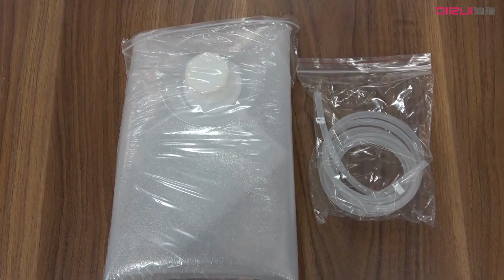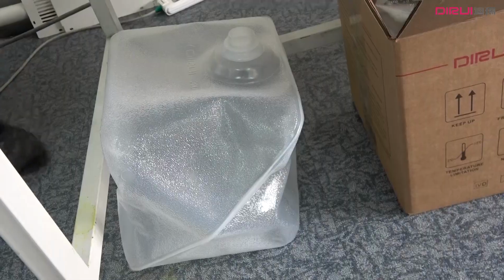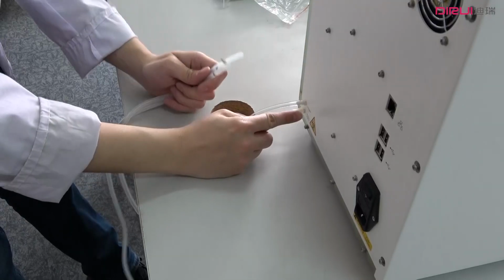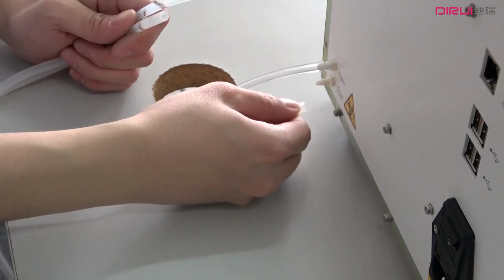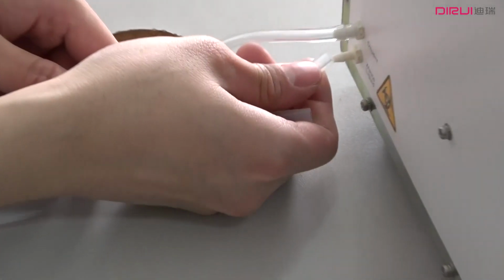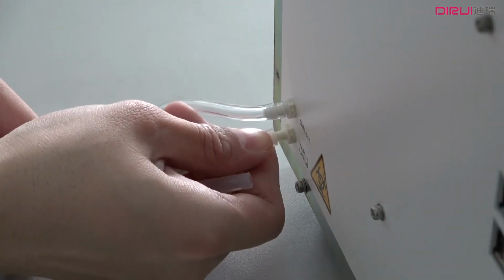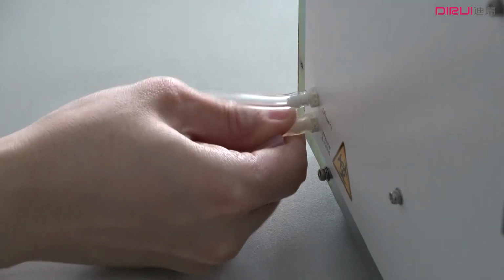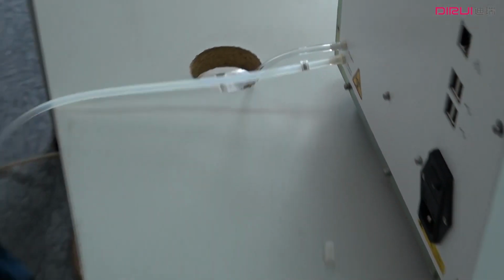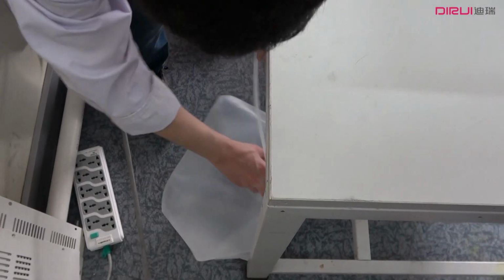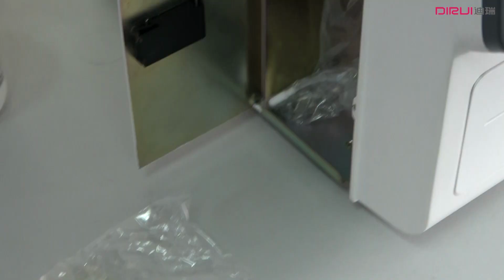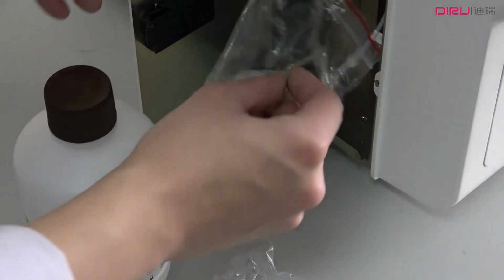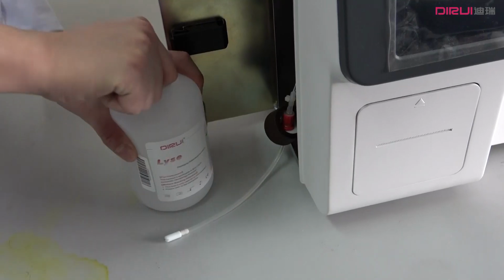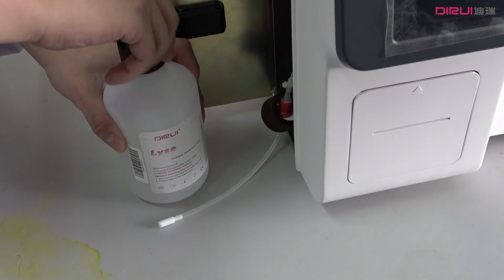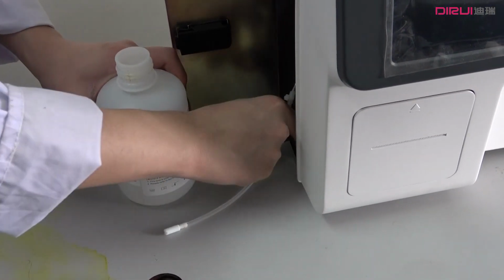Take out the waste tube bucket and tube. Remove the protector and connect one side of the tube with the instrument and insert the other side in the waste bucket. Take out the lyse reagent bottle and tube. Open the lyse reagent section and connect lyse reagent bottle with the instrument.